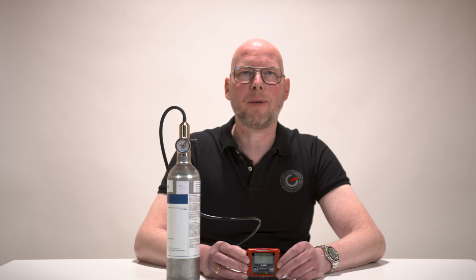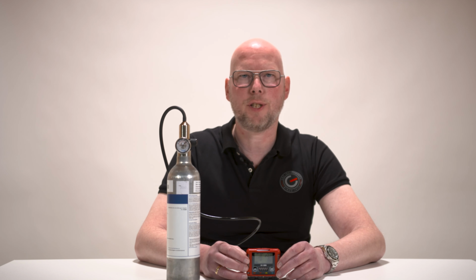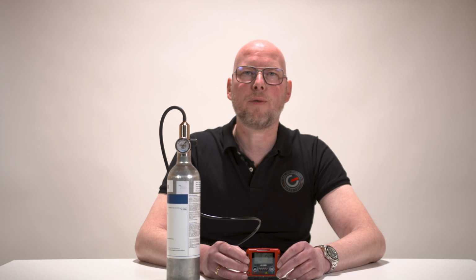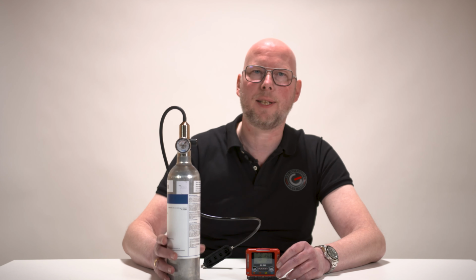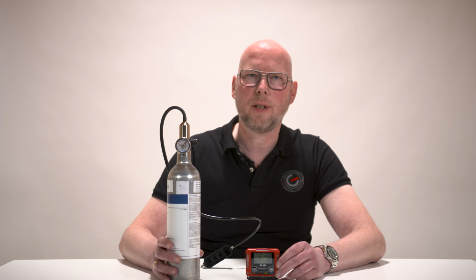In this video I'm going to show you how to perform a gas check with the Riken Keiki GX-2009 personal multi-gas detector. Here we go. Before you perform the gas check, make sure that you first have done the starting up procedure and the fresh air calibration procedure.